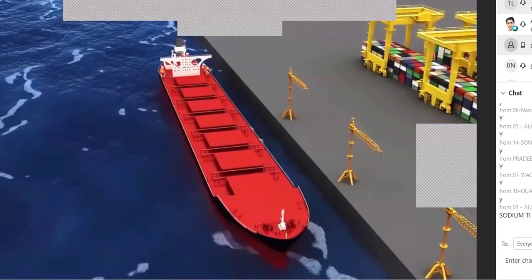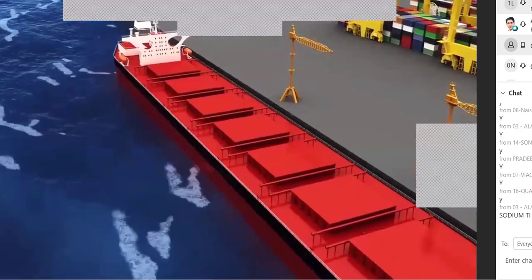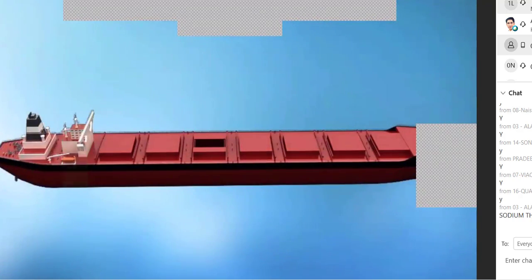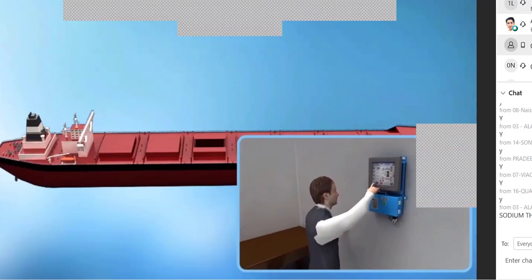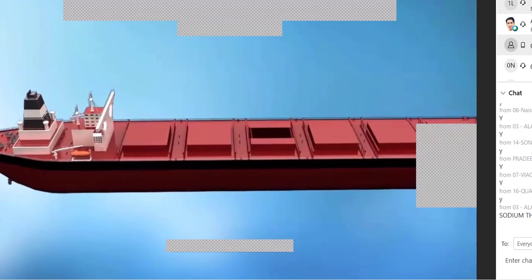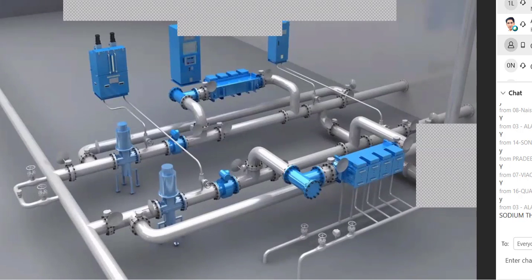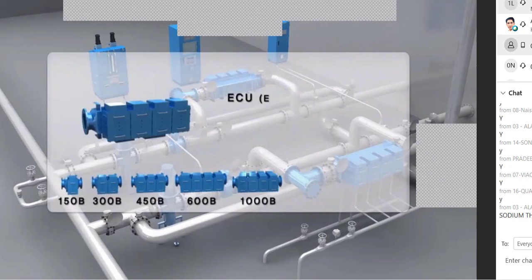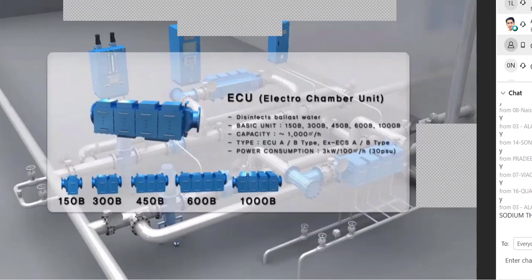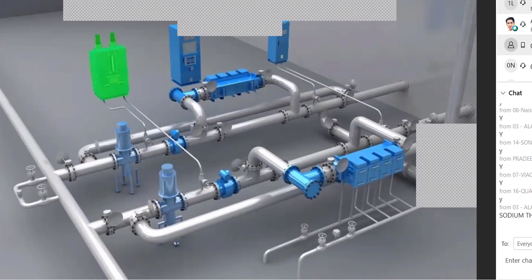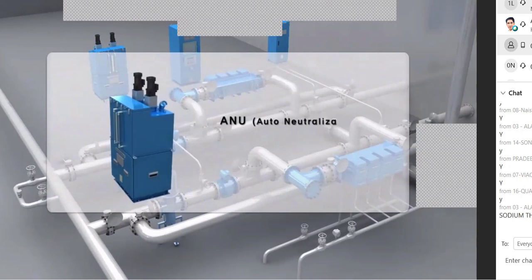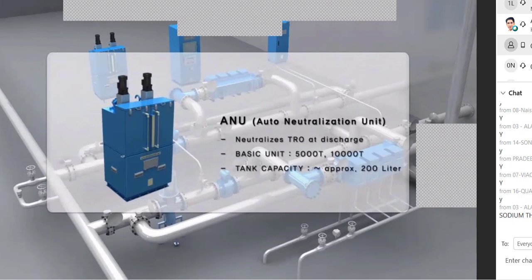This video is for providing an operation and installation for the Electro-Clean system, the ballast water management system developed by Techcross. ECS is one of the most effective disinfection systems using electrolysis. ECS treats one time at ballasting with certainty using a simple composition of equipment: ECU, ANU, PDE, TSU. ECU is the main equipment for disinfection of ballast water. ANU is designed to neutralize any remaining residual TRO prior to discharge. It is used during deballasting and stripping only.